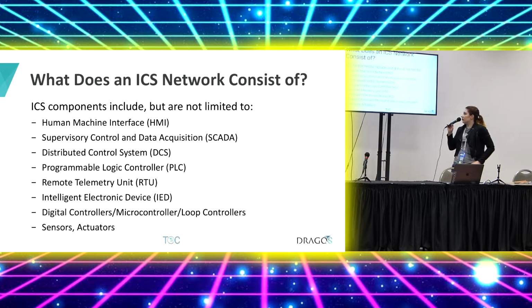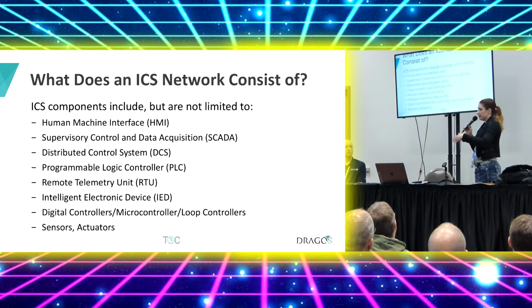You have multiple methods for controlling physical operational things like actuators and valves. You have distributed control systems, and you also have multiple devices on site like PLCs, programmable logic controllers. They're pre-configured to do these operational things at set times with set inputs. They're pretty dumb other than the logic you provide them, but they're told: when I receive X input, I do Y. Simple, generally Boolean logic - at this temperature, I shut off this actuator, et cetera.